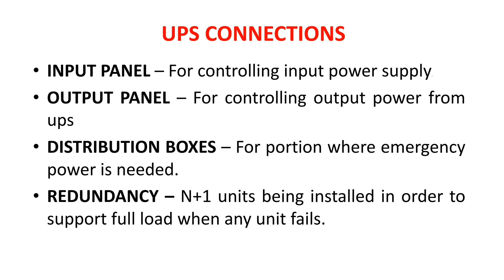Now here comes my favorite part, the single line diagram, SLD. In this you can see three 20 kVA UPS connected in parallel, and its input panel having 63 ampere 3 pole neutral TPN MCB connected to each UPS. MCBs, as we already know, are current protection devices. Here you can see one more MCB of 100 ampere. This is connected as a maintenance bypass, so that if these UPS require maintenance, then the raw power from the input will be connected to the load directly.